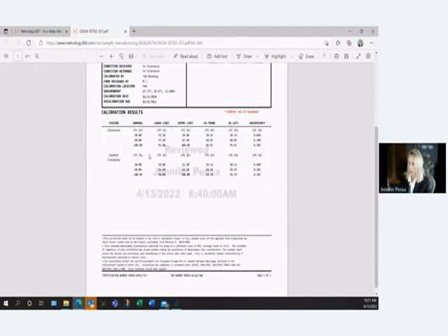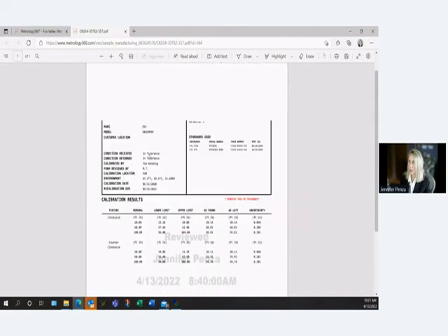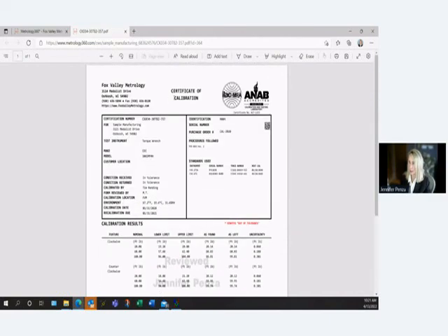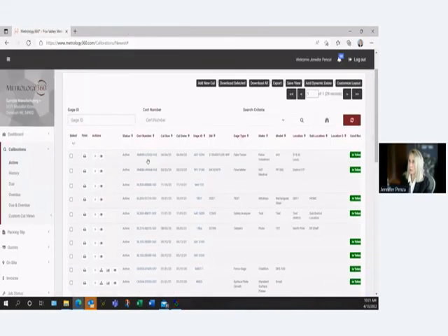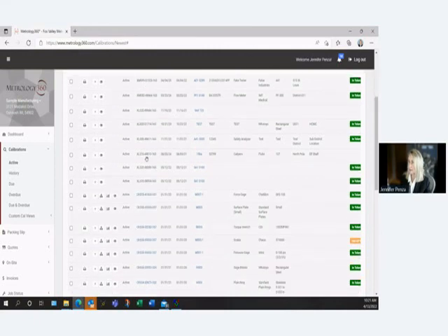We've already talked about certs that start with a C are calibrated by Fox Valley. Certs that are marked with an X are calibrated by you or outsourced to another vendor. If you were to upload those certificates in here, you would be able to click on these as well and see those certificates here. I don't believe any of these X certificates have them uploaded, but just notice the difference between the Fox Valley certificates in blue and the X certificates that are in black.